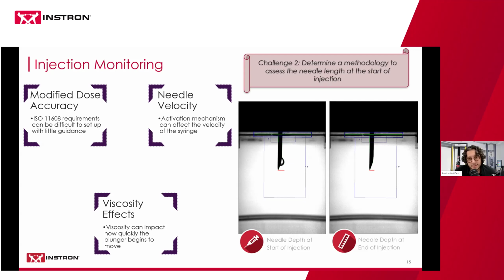While being able to identify optically the length of the needle at the start of the injection isn't a direct replacement for modified dose accuracy, it at the very least gives you a good data point: knowing that my device is performing with the fluid starting in the therapeutic range 90, 95, 99, 100% of the time. It can be used as a good potential quality check, and as an additional data point when doing device characterization earlier on in the R&D process.